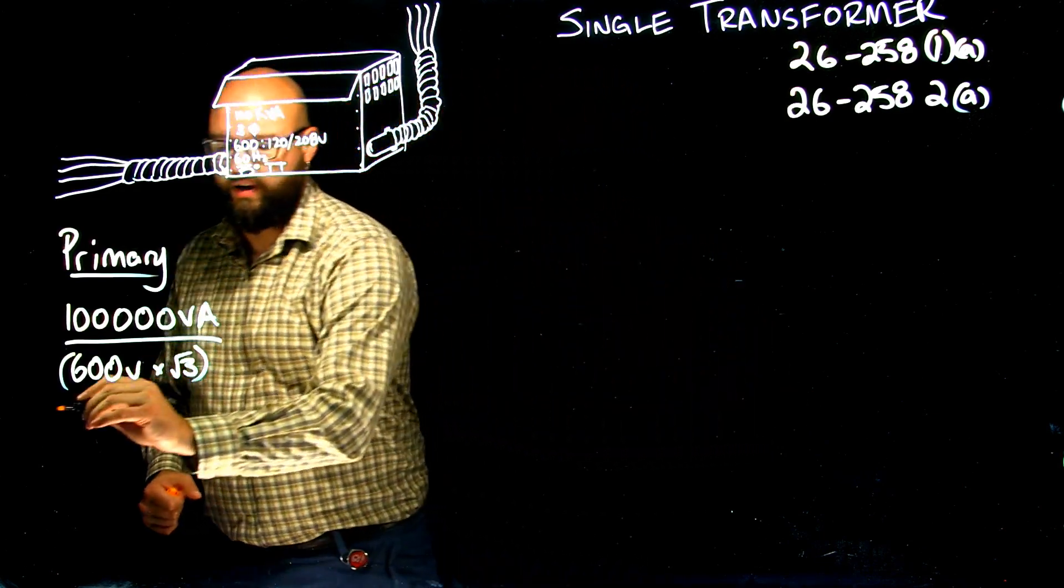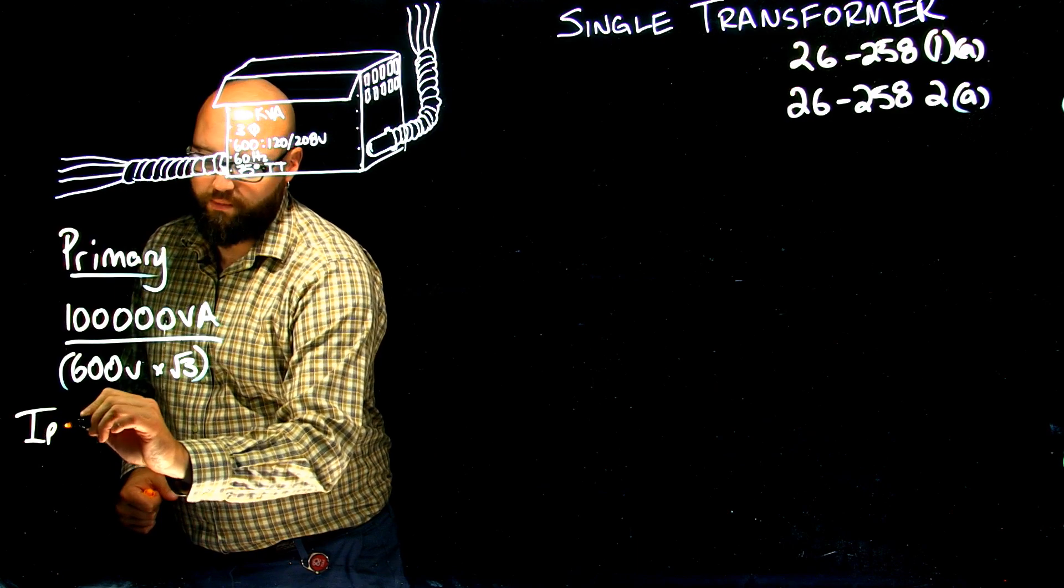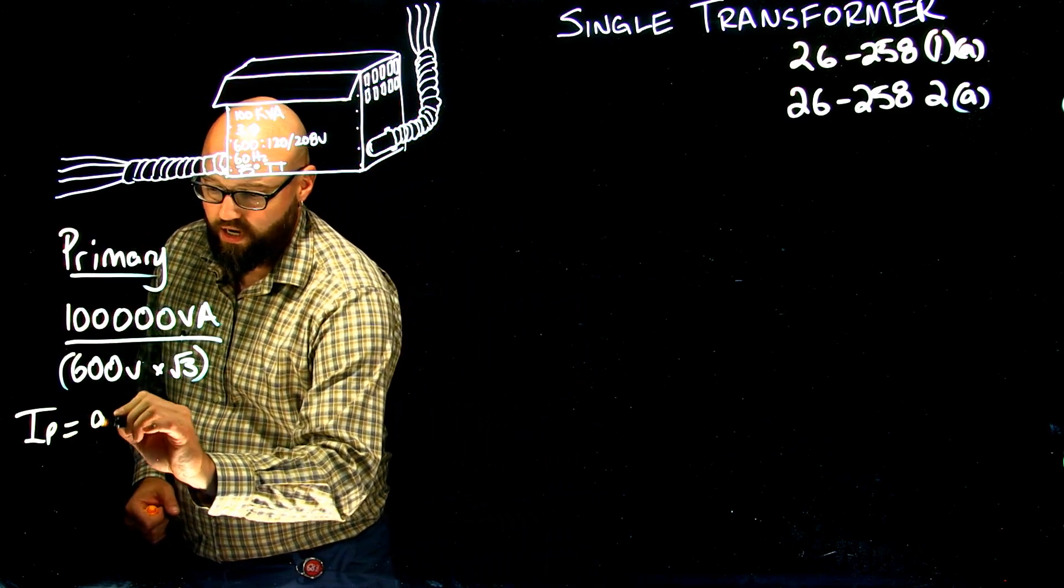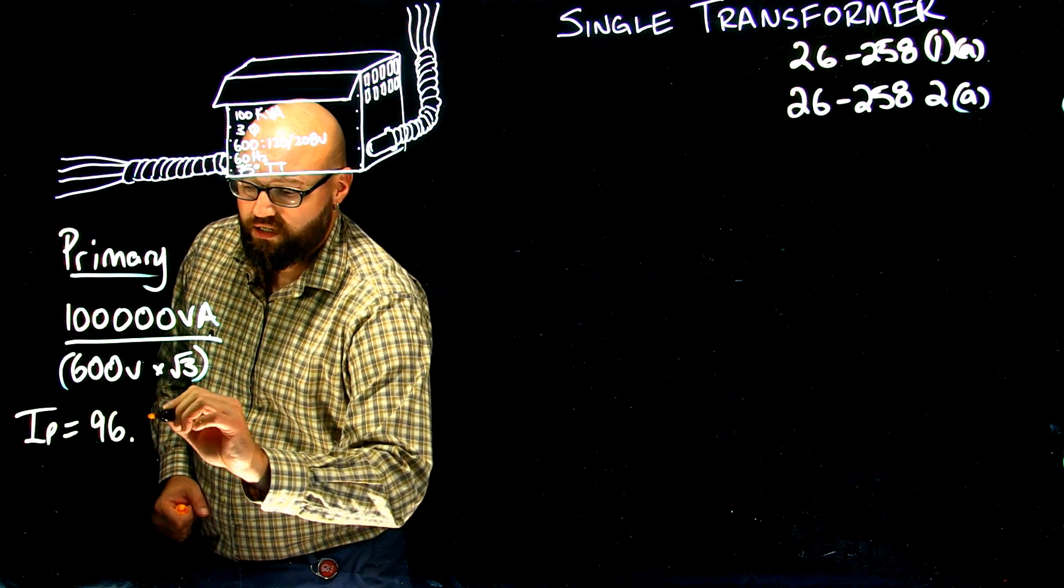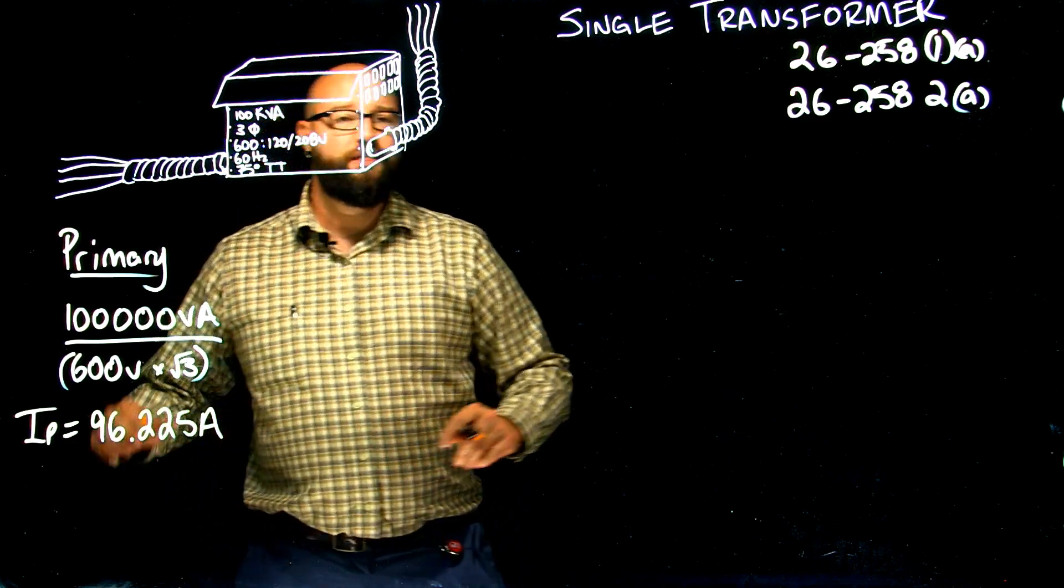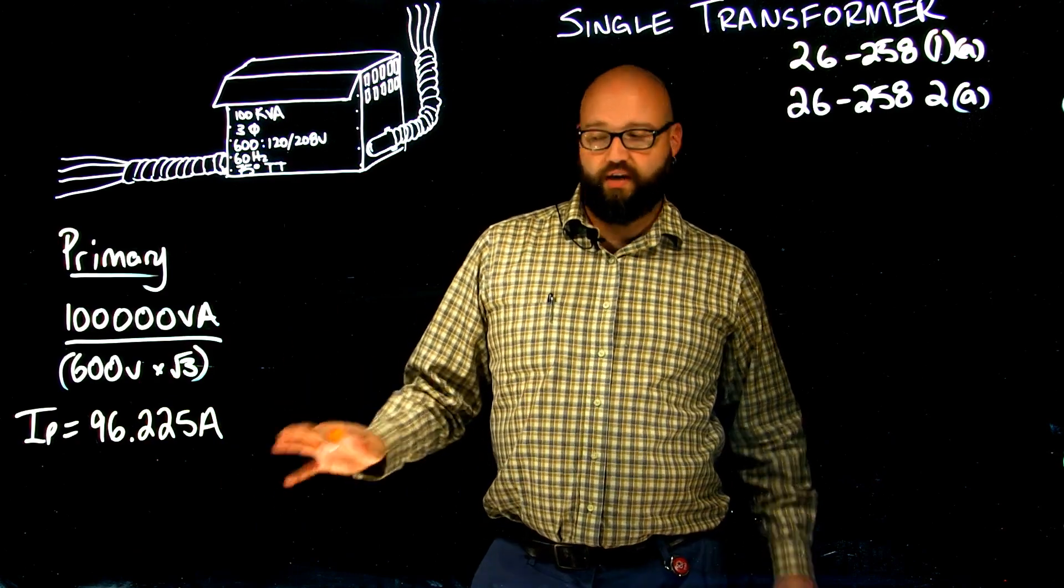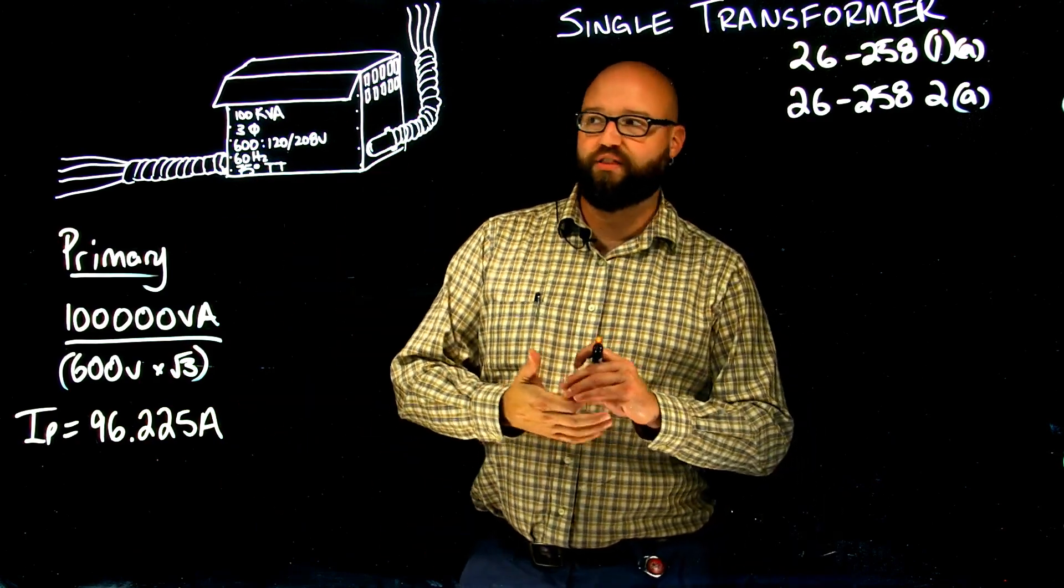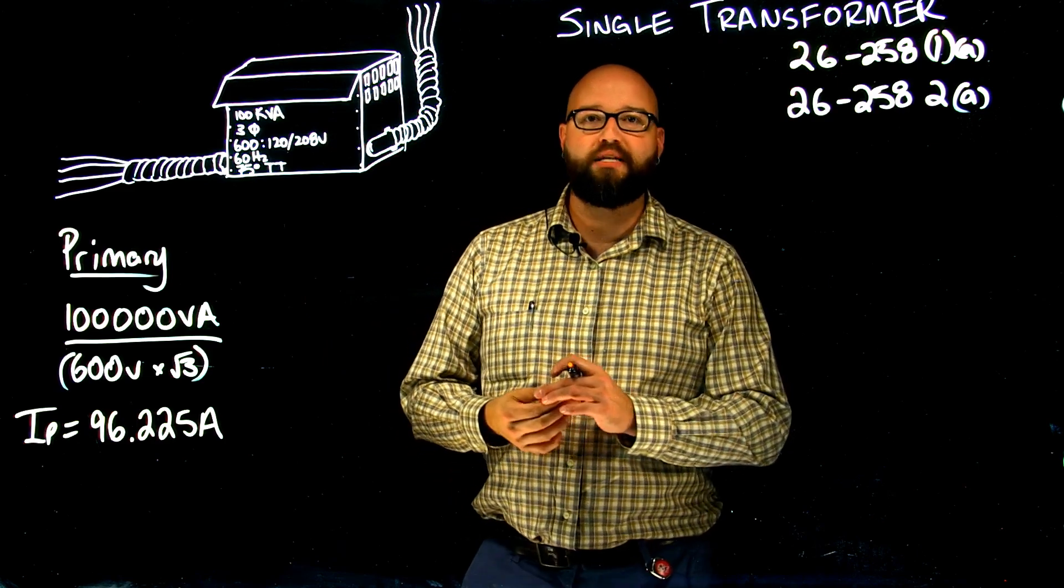We punch those numbers in. What we find out is current on the primary, rated at full load, is 96.225 amps. That is my rated primary current. That is what the current on the primary will be when I'm operating my transformer at the full 100 kVA load capacity.